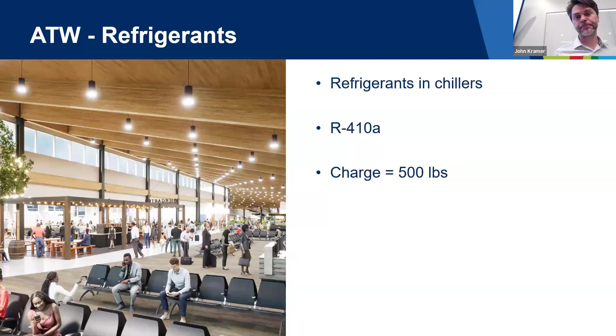Roughly, it's like a heat pump, so the compressors are running all the time, and the life expectancy is about 20 years. That's important because you include that in your life cycle cost analysis, but also your whole building LCA, when you're tracking the embodied carbon. Whenever you install the machine, you put the refrigerant in, and it leaks some annually just operating. And when you replace it, you can't salvage a lot of that refrigerant, so a lot of it gets lost. We have about 1% loss during installation. For predicting how much is lost annually, the number we found from EPA is about 15% annually, which is higher than you would expect, but if you've ever refilled the refrigerant at your house, it's probably more than that.